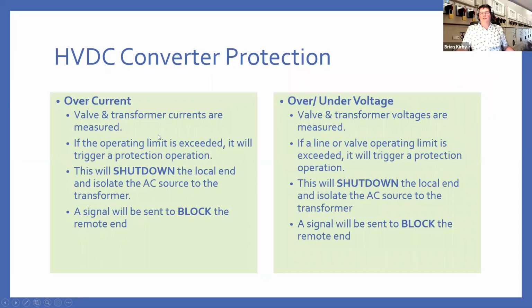Overcurrent, as I mentioned, your valve and transformer currents are measured. If you have an overcurrent on the local end, you will shut down locally and you'll send a signal to the remote end to block so it doesn't drive energy in from the other end.